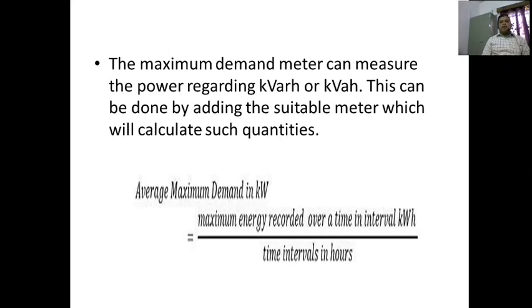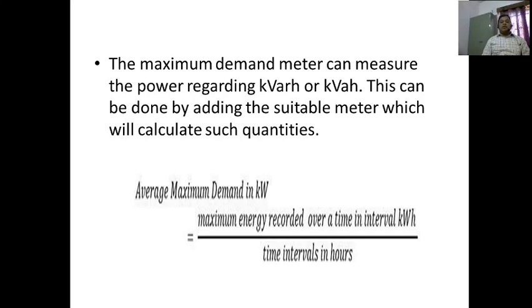The maximum demand meter can measure power regarding KVARH or KVAH also, whereas the energy meter measures KWH. This can be done by adding a suitable meter which will calculate such quantities. The average maximum demand in kilowatts equals the maximum energy recorded over a time interval divided by the time interval in hours.